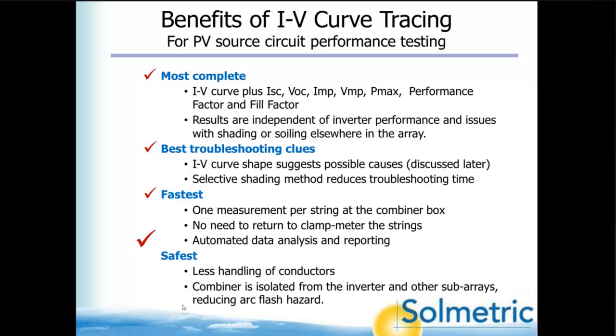So I'm going to assume from all of this that you're mainly here for the second half of the hour, which is fine. So we've gone through most complete, best troubleshooting clues, fastest, and now I want to just point out that it's also the safest. And the reason for that is that there's less handling of conductors.